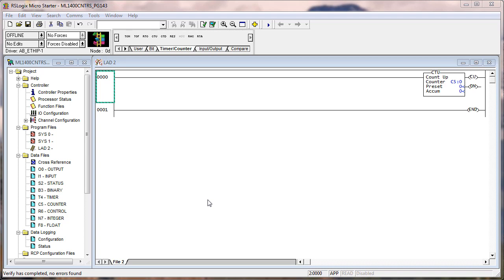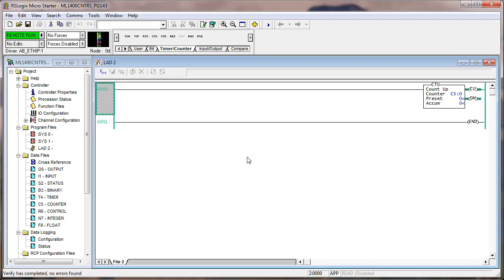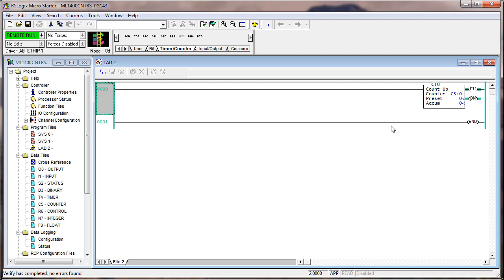I'm doing things in the reverse order from the manual. I created this wrong offline. Now I'm going to download it — that was the second step. I had you delete the rung you created, go offline, create the rung, download, and put it in run mode. You can see the counter dot increment, but it is immediately done because the preset is zero. On the first scan, the preset equals accumulate, so it's done. That's no way to use a counter, but we were making a point.